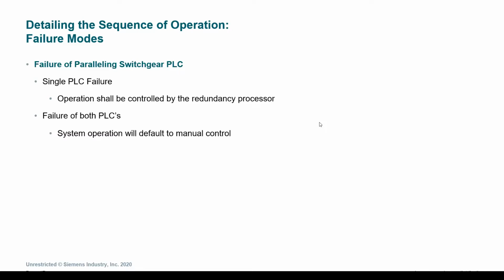In the case of a single PLC failure, we are confident that the redundant PLC processor would be available to pick up that operation and control the switchgear. In the case that both PLCs failed, the system operation would alarm and a facilities team would be brought to their attention to take over it and operate it manually.